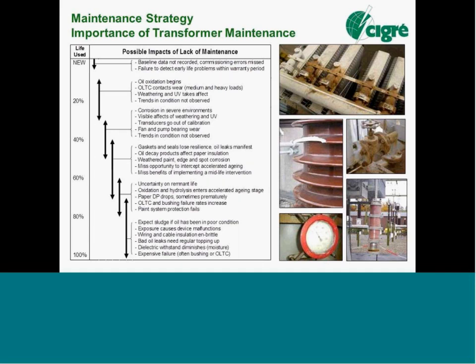The way that oil leaks manifest in a transformer can often be a driver for a lot of asset owners to act, just on the observation that the transformer is badly leaking oil. Sometimes they only act when they have to top up the transformer to avoid the low oil level alarm. And gaskets and seals have a lifetime, and that's common with a number of parts of the transformer.